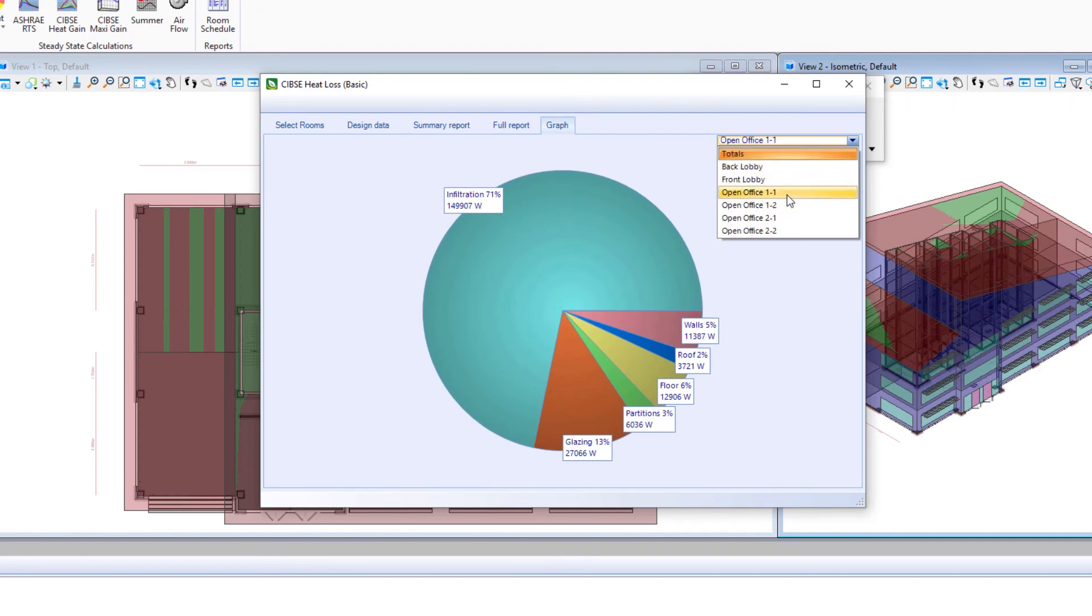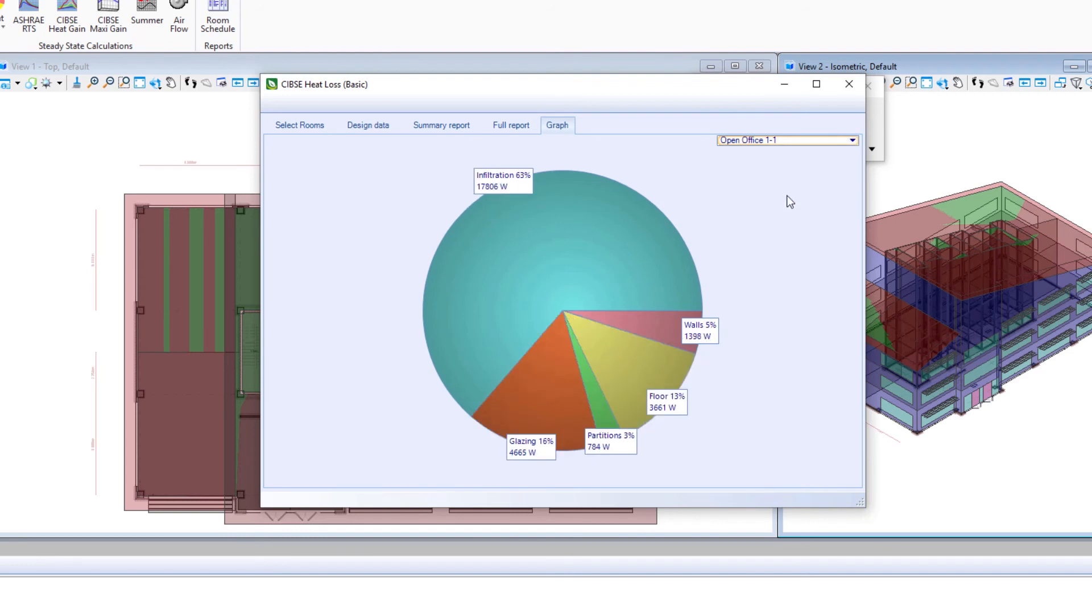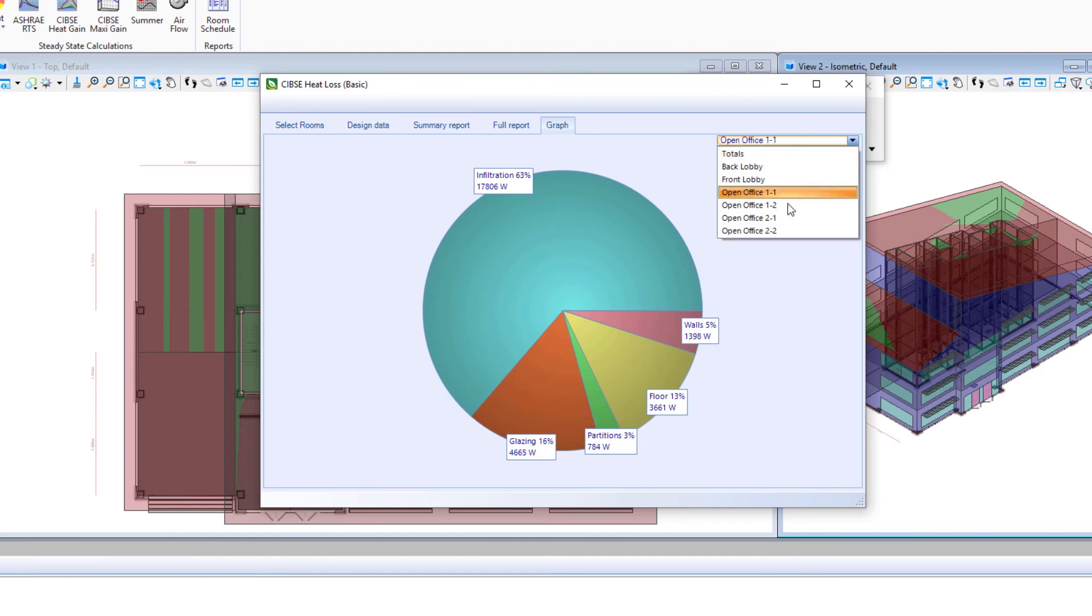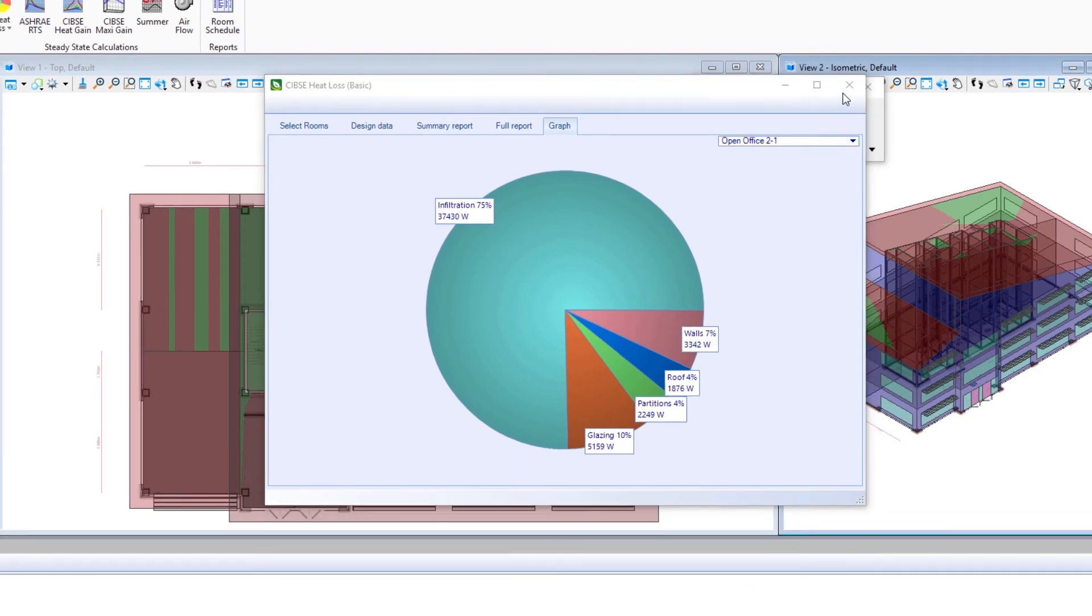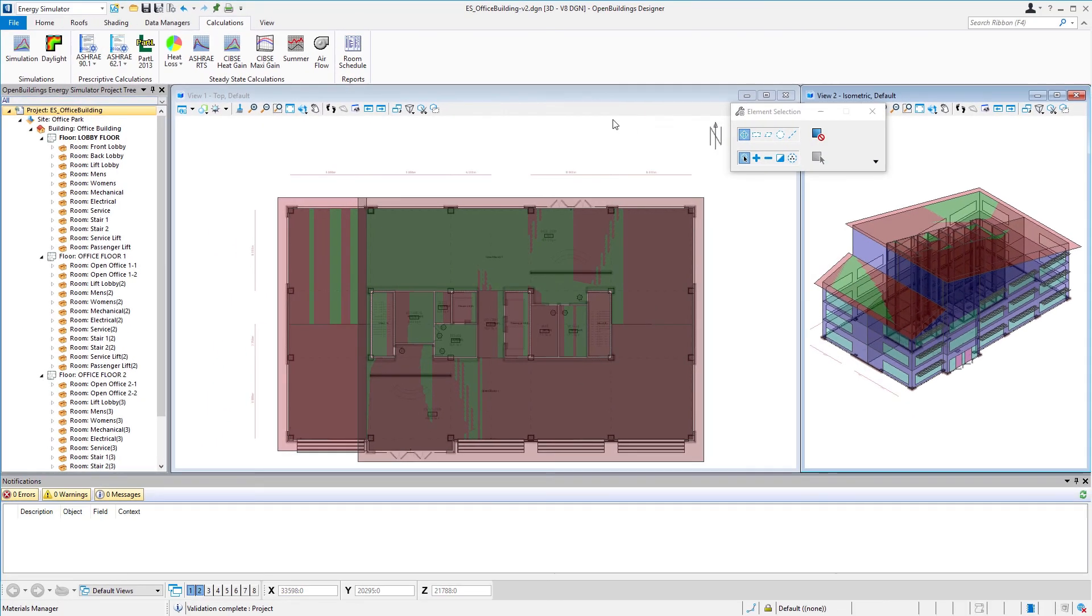If we look at the open office one dash one, we can see now that has been reduced to 5%, as opposed to the 16% we had earlier. Of course, we didn't change the floor two, so that's still 7%, but we are able to see that difference that was made in terms of heat loss. So we'll go ahead and close that dialogue and we have finished our calculations.